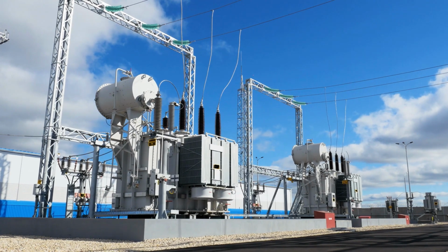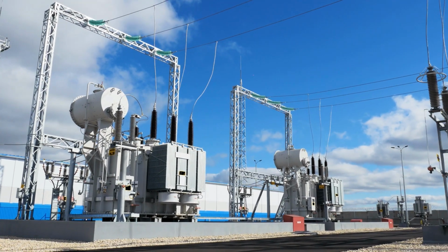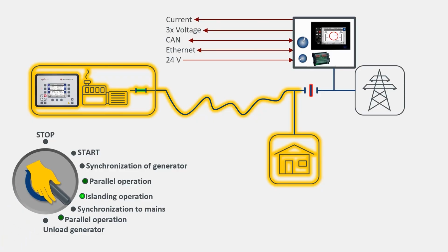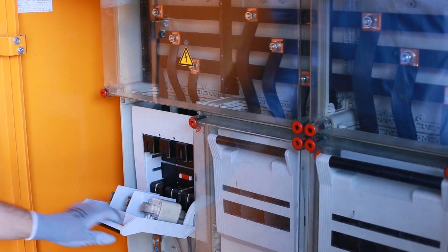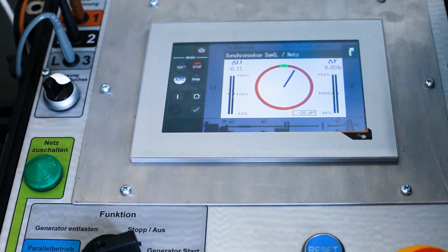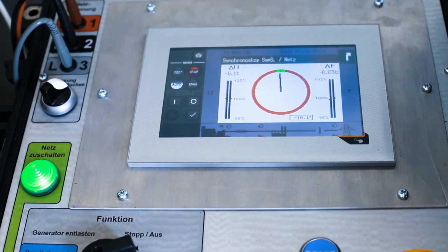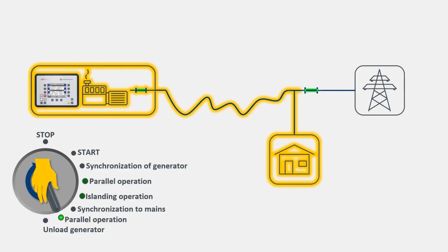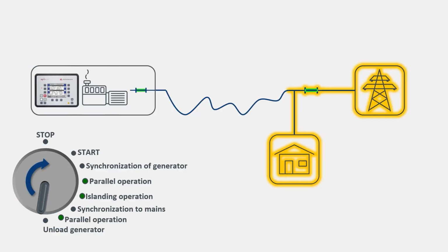When our primary job, like servicing a transformer, is done, the EasyGen 3000 XT will synchronize the mobile generator seamlessly back to the utility. For reclosing the mains breaker or fuse, the synchronoscope on the remote display guides the operator to switch back to mains power supply. Many technicians appreciate an audible and visual synchronization indication to close the mains breaker or fuse. For this purpose, one uses simply a digital output of the EasyGen 3000 XT. At the end, we unload and stop the generator.